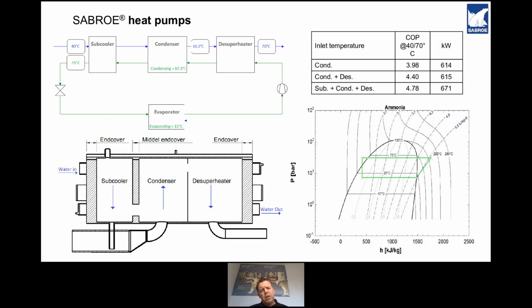What does this mean in COP? If we just had a standard condenser, you would be getting about 3.98 COP in these conditions. Add the desuperheater, 4.4. Add the subcooler, 4.78. So this is a very good thing to have if you want to maximize the heat exchange in your system. So let's see, moving on to the next slide.